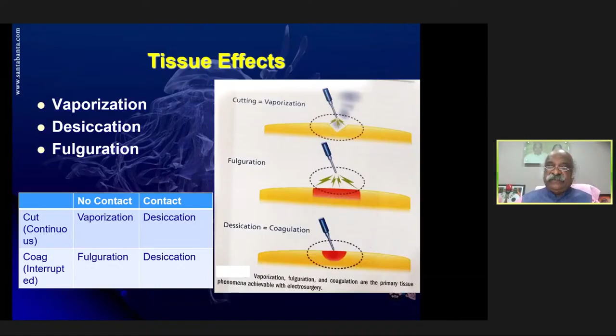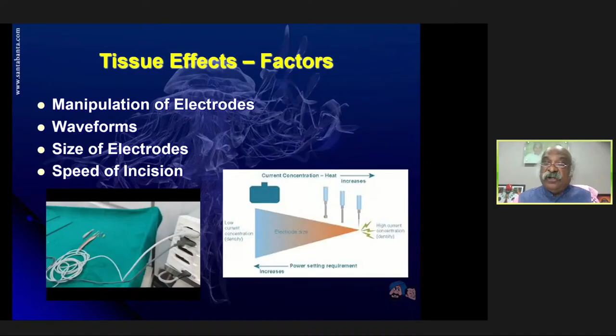So these are some of the electrodes which I have shown earlier. The tip of the electrode is different, and depending on the tips and manipulation of the electrodes, tissue effects are variable. If you use a needle electrode, the density of current is maximum, compared with a flat electrode or a bulb. The tissue effects are very important for manipulation of the electrodes. With the electrode design, the tissue effects are greater, as more concentrated current is at the tip. Waveforms are also different, and different waveforms have a different effect: the cutting waveform, coagulation waveform or blend waveform. Size of electrodes is also important, and so is the speed of incision. Fast versus slow incision in surgery makes a difference to the effect. And timing, how long the electrode is touching the tissue, is also important. The effect is variable for that.